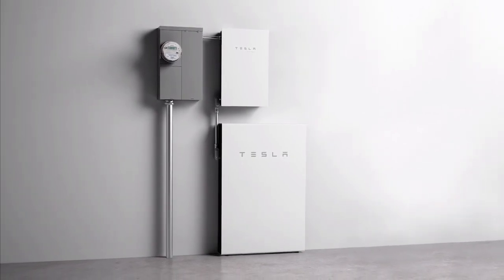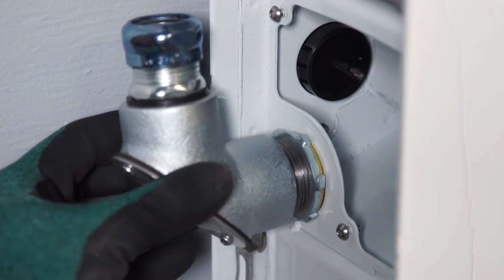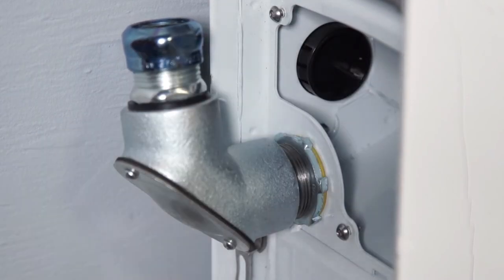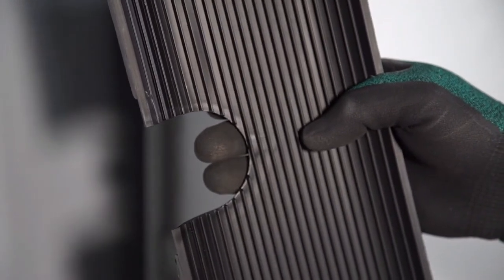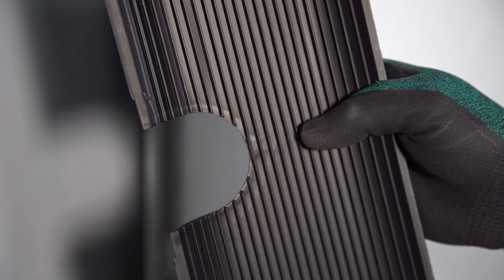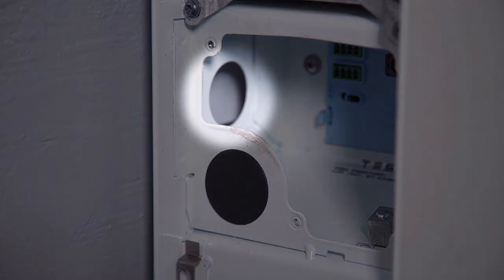When preparing for the installation, take your time to plan out a short and efficient conduit run. A typical installation uses one-inch conduit with a conduit body connected to the inlet on the left side of Powerwall 2. If the conduit run will enter the unit from the side, slide the conduit entry door out of the slot in the cover to remove it.